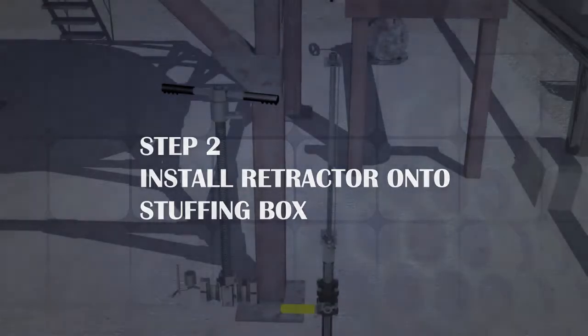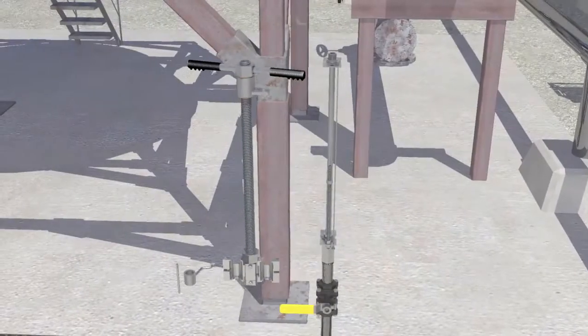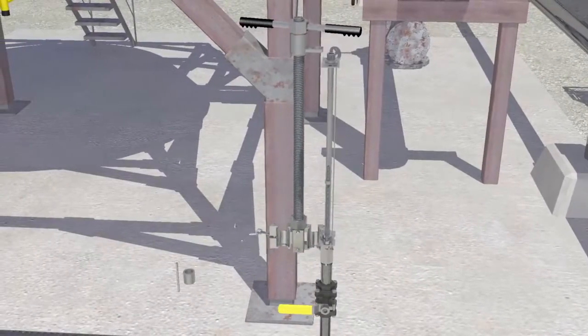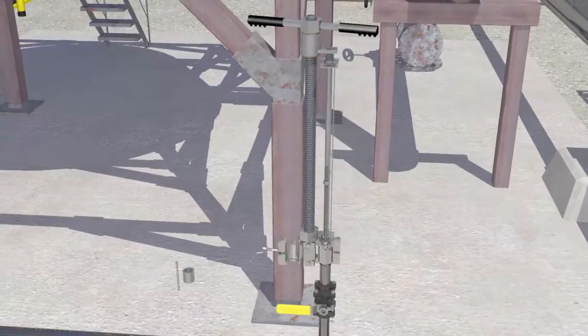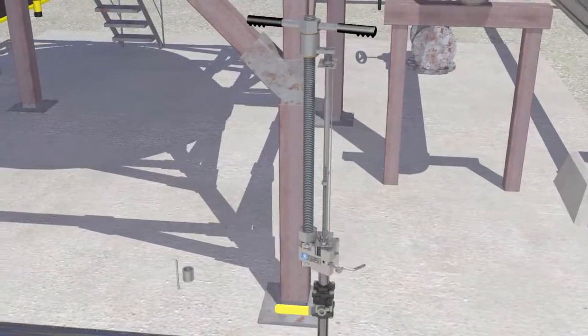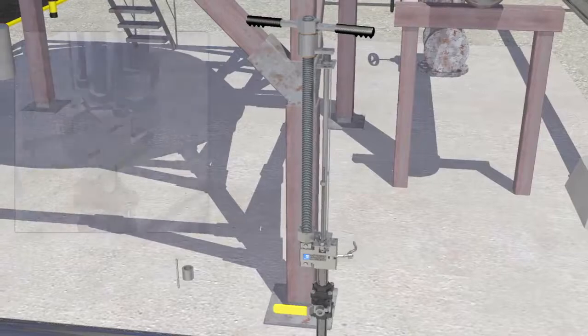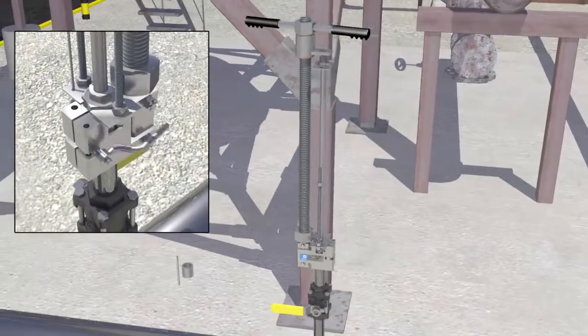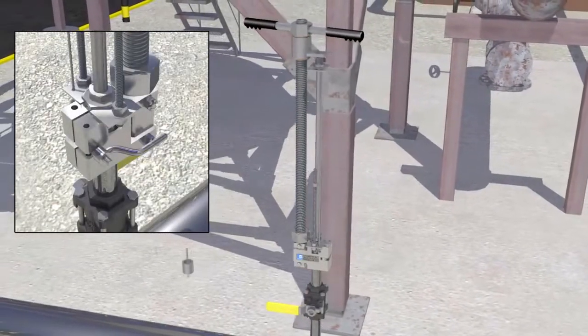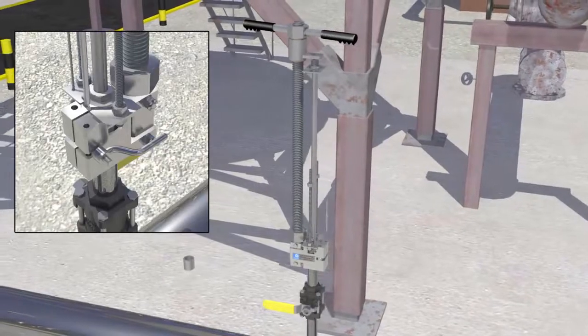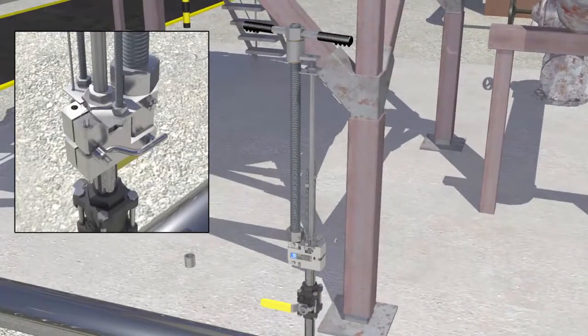Step 2. Install retractor onto stuffing box. Assemble the 2 halves of the clamp assembly around the probe stuffing box such that the cutout in the clamp aligns with threaded rods, when present, ensuring the safety cable is not crossed or interfering. Draw the clamp assembly together and secure with the lever nut. Insert the quick release pin into the hole provided on the right half of the clamp assembly.